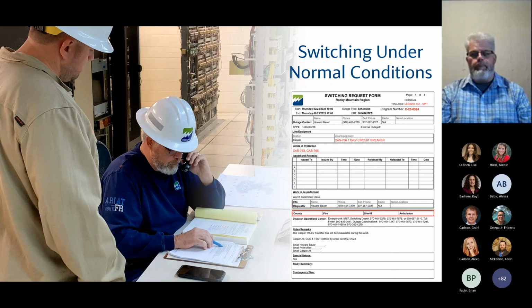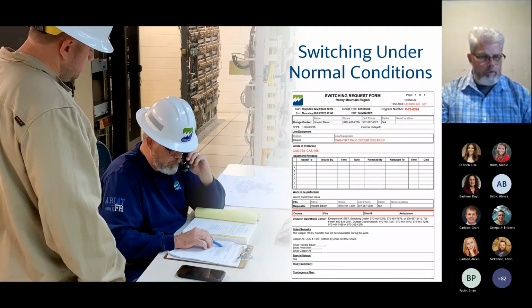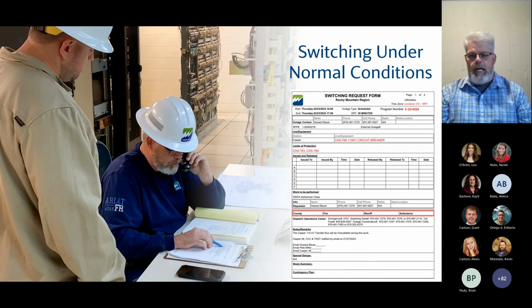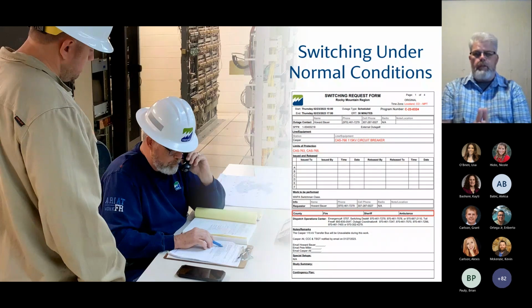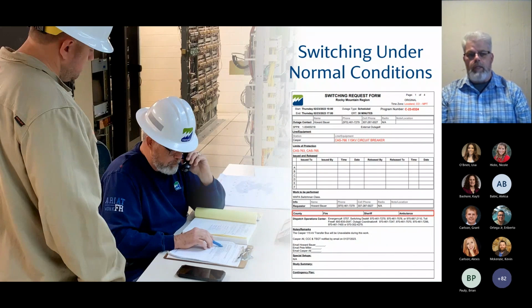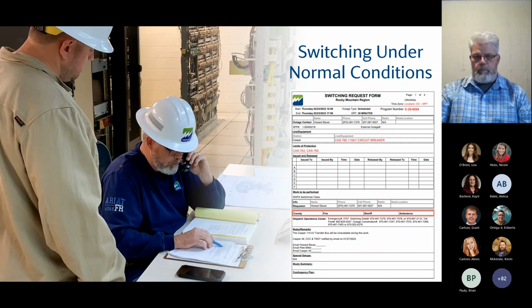Once you submit an outage into operations and it goes through the study phase, the planning stage, the switch writing, the outage coordination, your program is approved, but it's not truly approved until the morning of the outage. Why? Because the system is always changing from when you submitted your outage to the actual day of execution. System conditions could have changed, and that could impact your availability of taking your program out on the day that is planned.